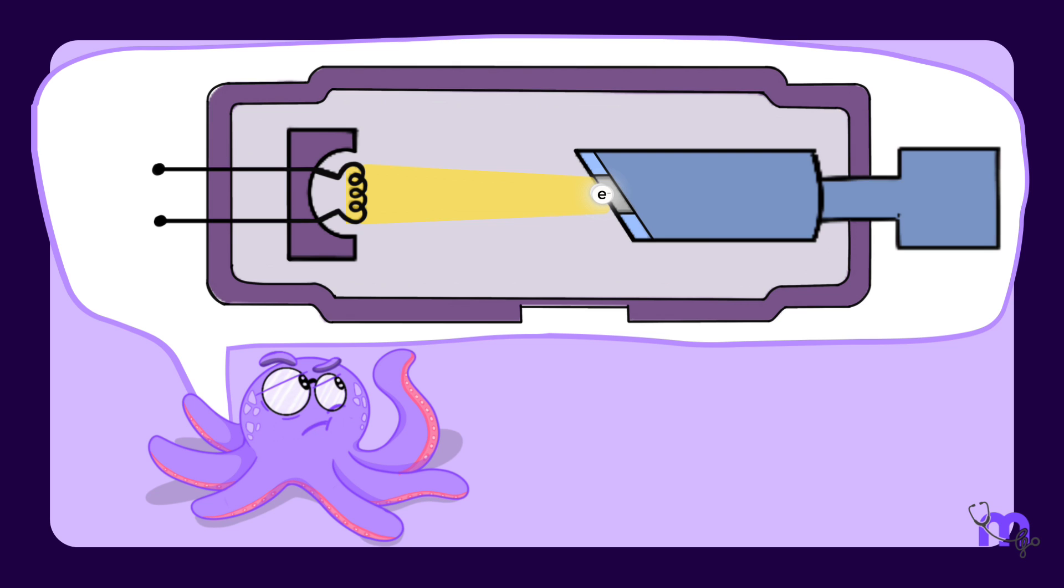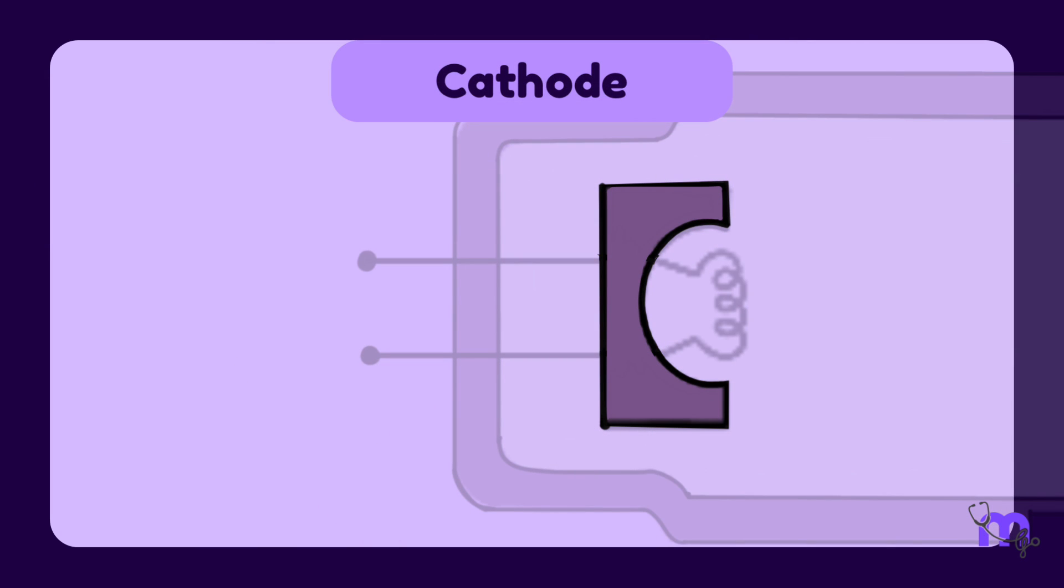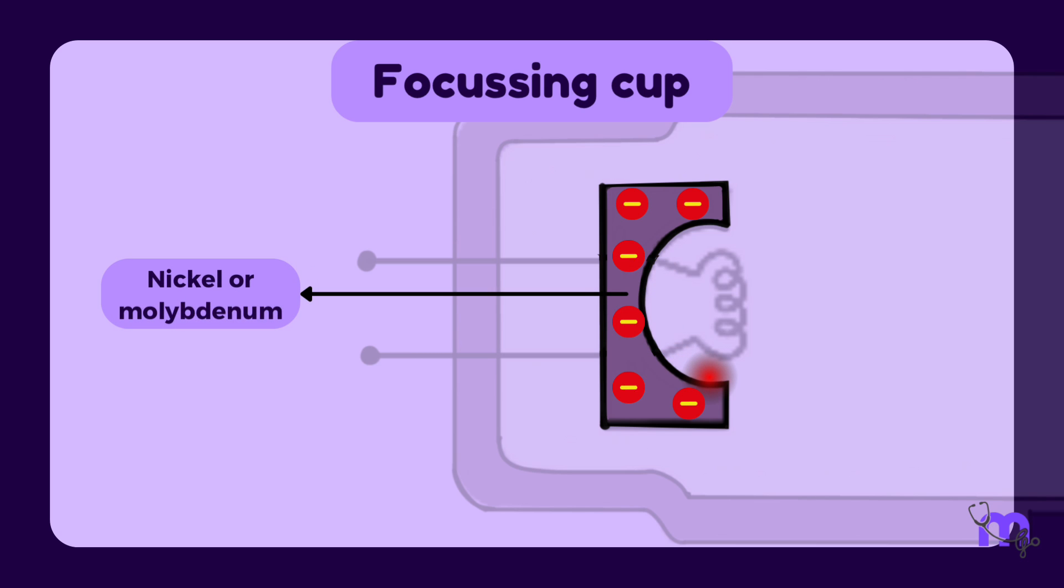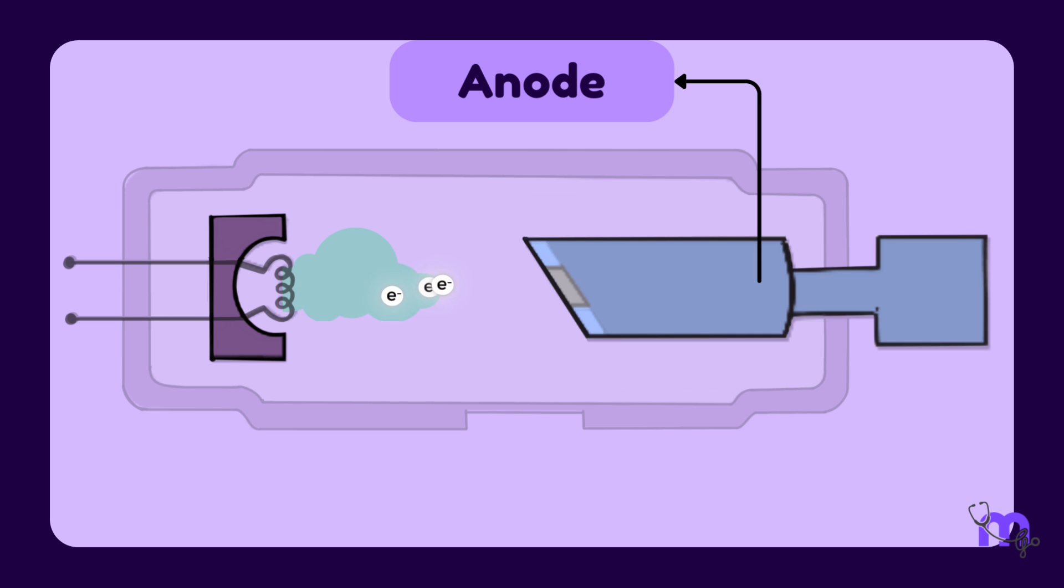What we need is a neatly channeled narrow beam of electrons that would further give us a narrow X-ray beam, thereby a good quality image. So here is where the other important component of the cathode called the focusing cup comes into play. This is a negatively charged concave reflector made of nickel or molybdenum. It repels all the electrons produced, pressing them back together. This restricts the size of the electron cloud, thereby producing a narrow electron beam which is directed at a small rectangular area in the anode called the target.